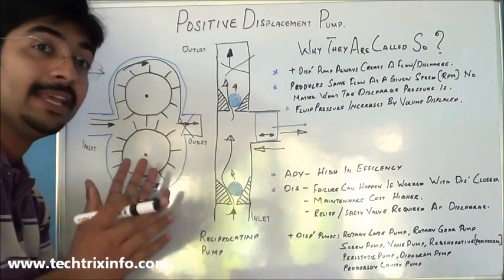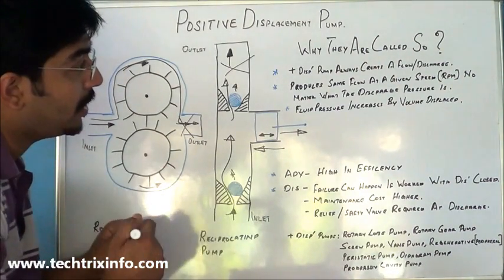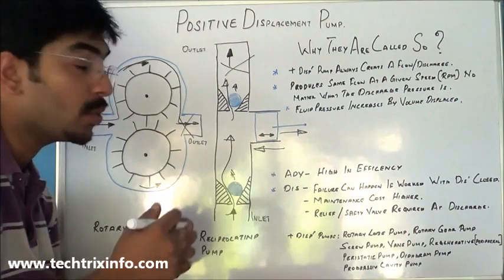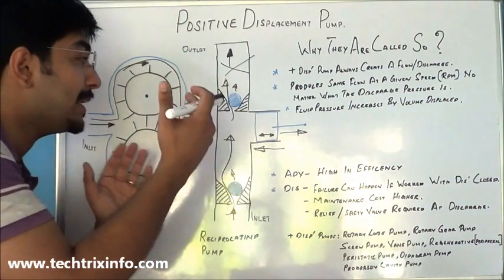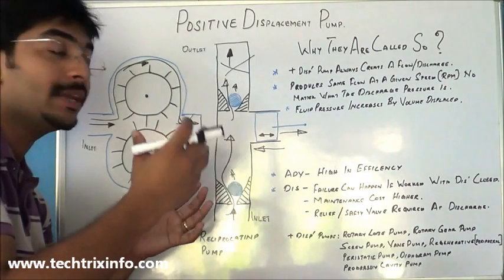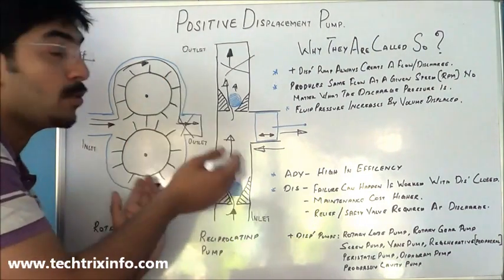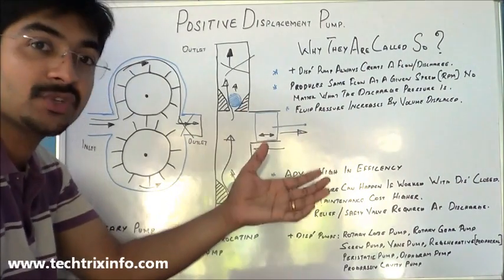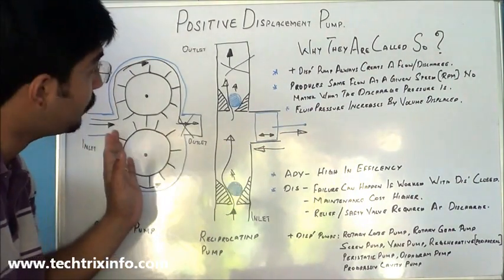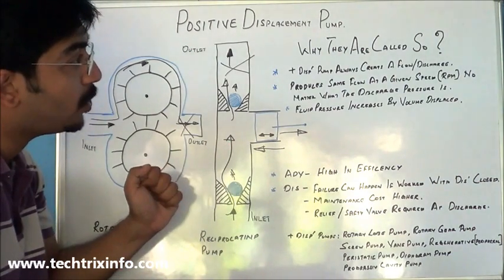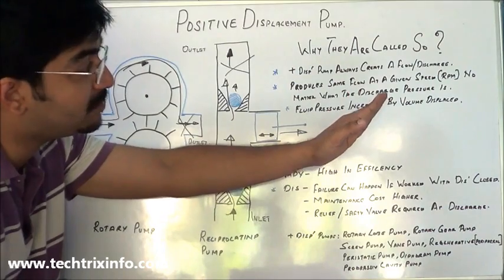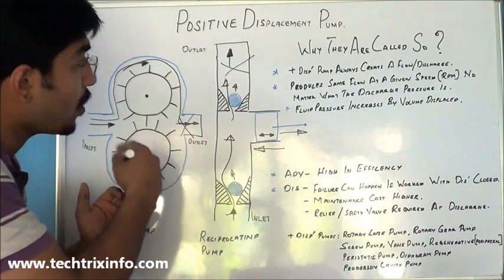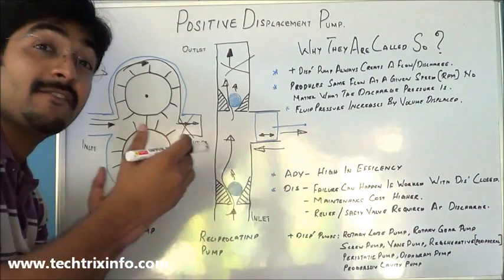One important point to note is that fluid pressure is increased by the volume displaced. The higher the volume getting displaced, the more the pressure will increase. A positive displacement pump creates an increase in pressure by delivering more discharge. It also produces the same flow at a given speed or RPM, no matter what the discharge pressure is — if the pump is working at a constant speed, it produces a definite, fixed amount of flow.